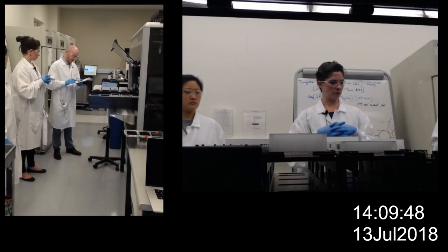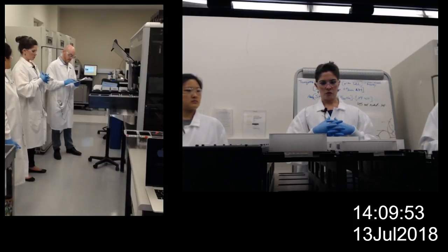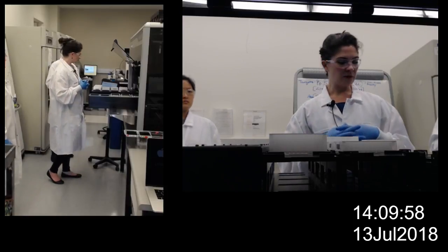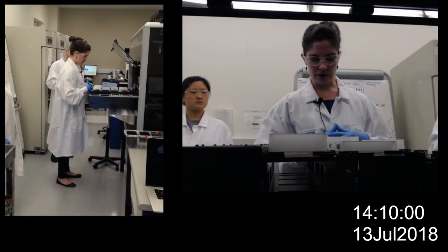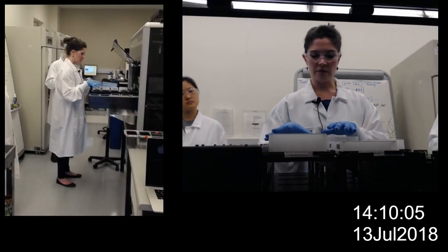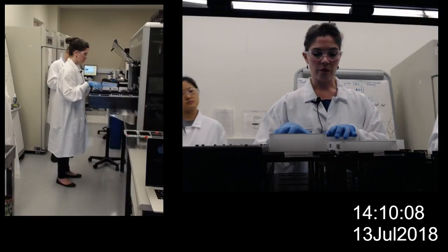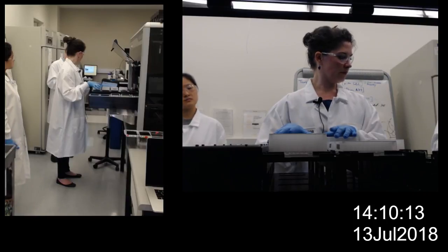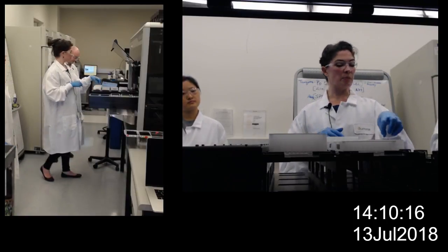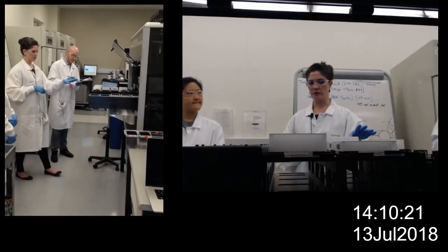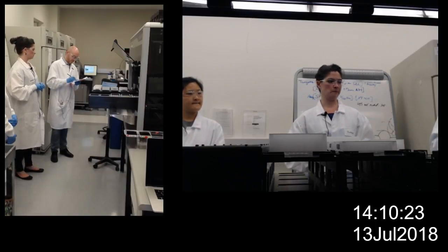And then loading the consumables, any other thoughts on loading the consumables based on the designs? I mean, if these are all coming sort of pre-filled and you're just doing ethanol into sort of reagent reservoirs, then that's very nice and straightforward. Again, the remember to unseal your plates warning popping up when you hit load will be awesome. And as a separate reminder, not just unsealing your plates, but to take your seal off your centrifuge plate before you put it on.